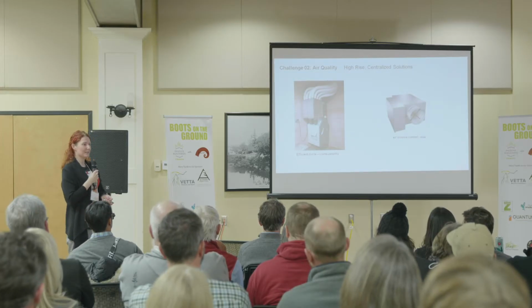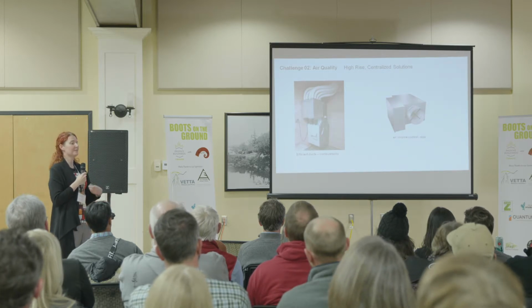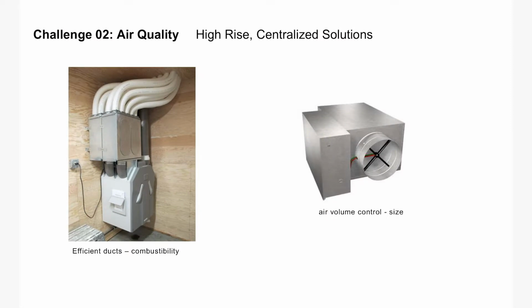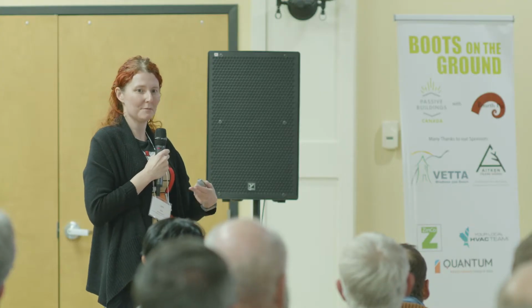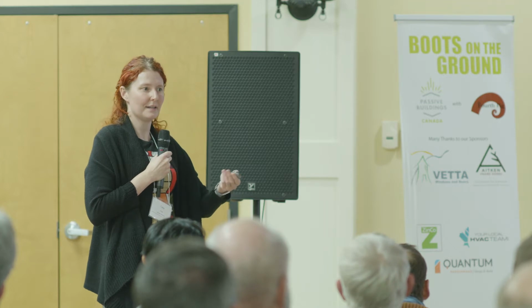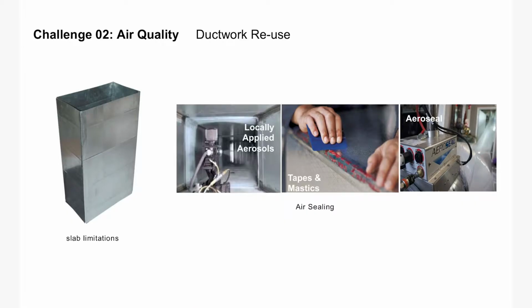With a centralized system, we also get the benefit of being able to provide cooling. And we're going to be controlling both the cooling and heating and the ventilation airflow. Instead of having an individual system, we're actually going to be providing everyone with a variable volume damper with modern controls. So they will be able to set it to a heating or a cooling mode or to a ventilation override mode. So we should have more ventilation available if they want, and then a low ventilation rate that's standard throughout the day. We're reusing ductwork. The ductwork, we think, currently has a leakage rate of about 25%, so that's a lot.